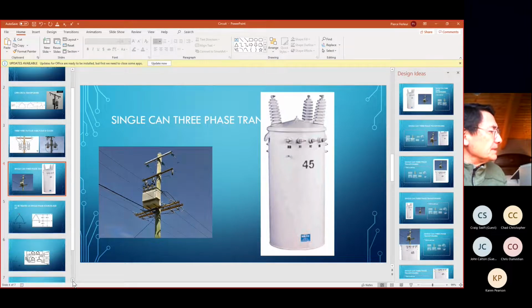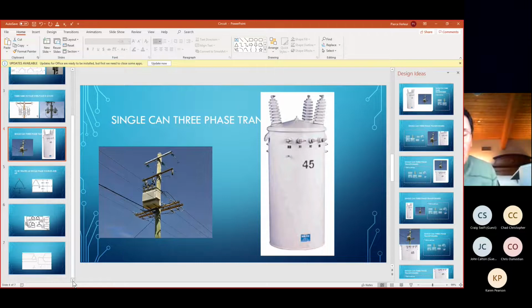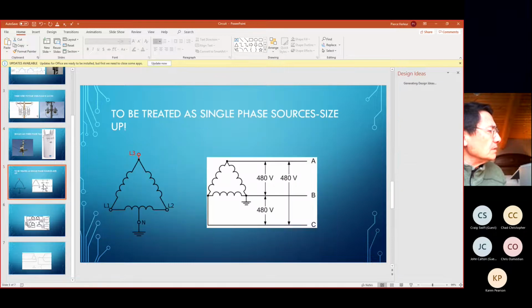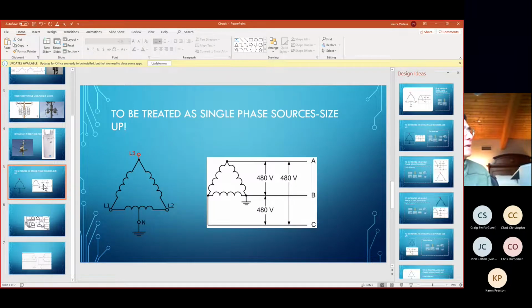The single phase stuff, which is more severe than open delta, and the first one... obviously a single phase transformer is a dead nut single phase source, but there are 3-phase supplies out there that have to be treated as single phase and therefore more severe than the open delta configuration.